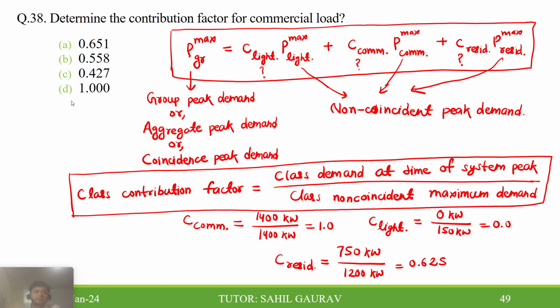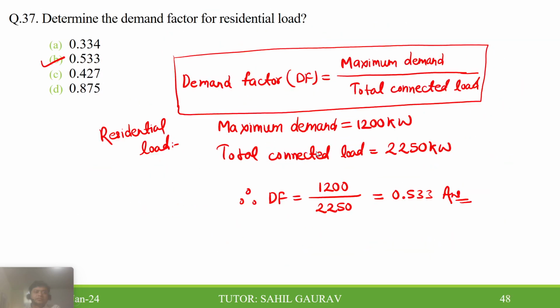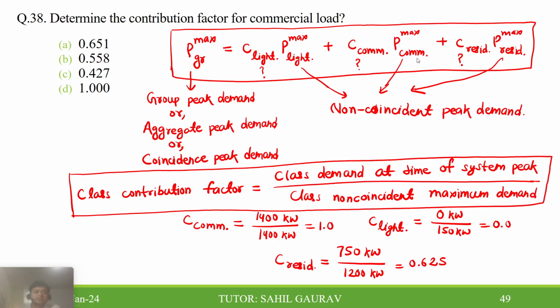Now coming to the last problem, which is very important because this part is not discussed in class. Here from the table you have to find the contribution factor for commercial load. We know that group peak demand is related to individual demand by this coincidence factor, this contribution factor. So I have written down that group peak demand is equal to the contribution factor for lighting load times the maximum lighting load, plus the contribution factor for commercial load times the maximum demand for commercial load, plus C residential, the contribution factor from residential load, times the maximum demand from residential load.